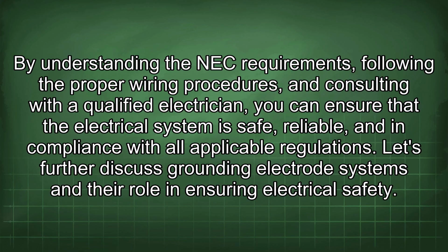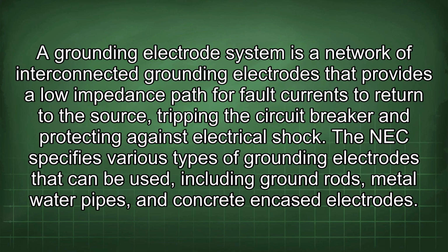Let's further discuss grounding electrode systems and their role in ensuring electrical safety. A grounding electrode system is a network of interconnected grounding electrodes that provides a low impedance path for fault currents to return to the source, tripping the circuit breaker and protecting against electrical shock. The NEC specifies various types of grounding electrodes that can be used, including ground rods, metal water pipes, and concrete encased electrodes.